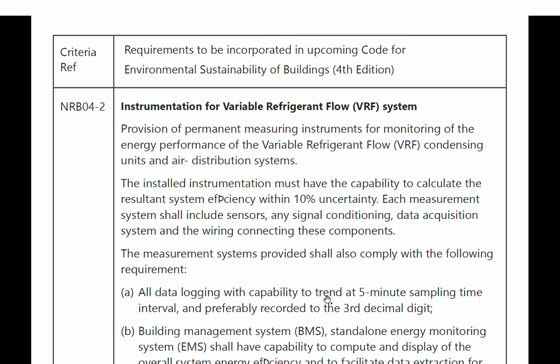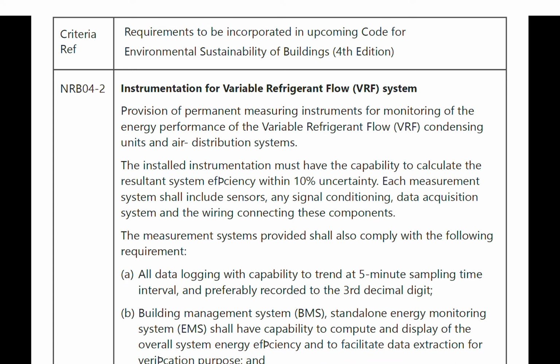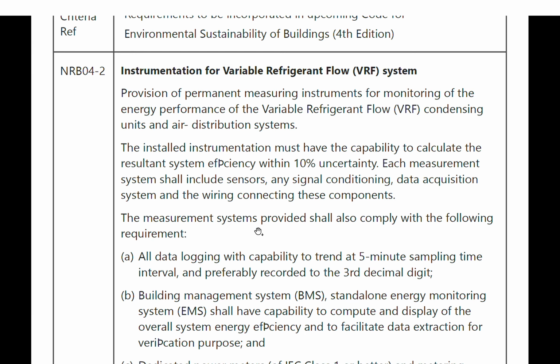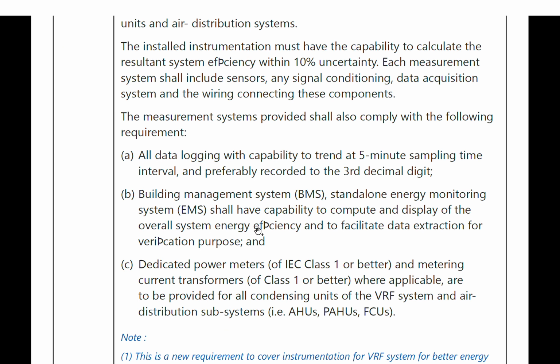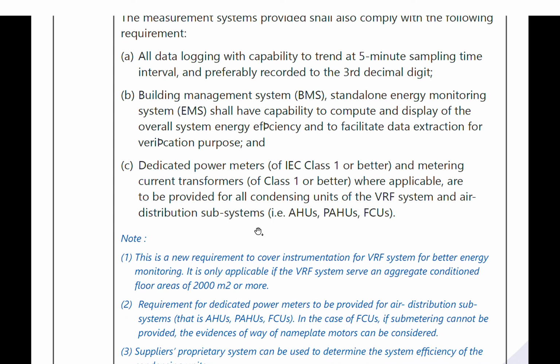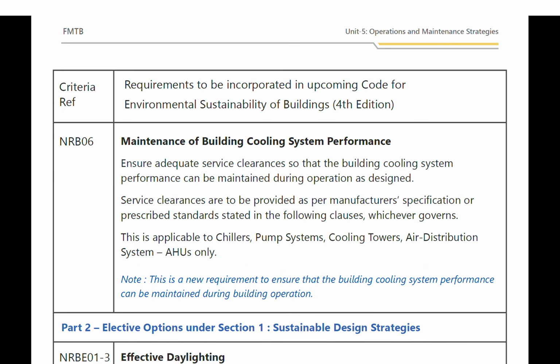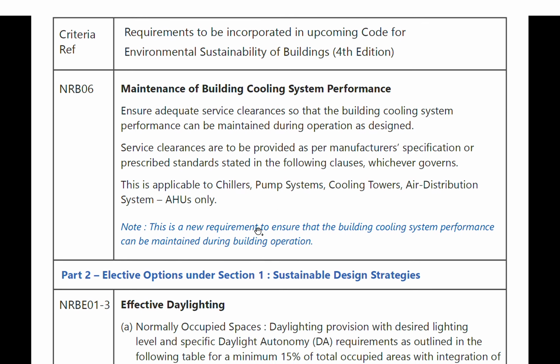Alright, instrumentation for VRF systems involves provision of permanent measurements of the VRF system using the condensing unit. You install the instrument, and you have the capability to calculate the resultant efficiency. with an uncertainty of 10%. Each measurement should include some sensor and signal conditioning. The data log should be about 5 minutes, and the BMS system standalone energy monitoring should be able to capture, display and extract data. A dedicated power meter and current transformers should be applicable for the VRF systems. Right, for building maintenance of the cooling system performance, you need to adequately cool the building, but it also has to be designed for that. So service clearances will be required, typically from the pump, cooling tower, and distribution system.